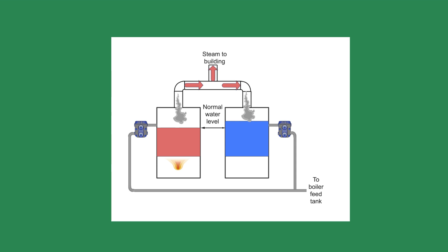They are installed about an inch or two above the normal water line. If the water level reaches this elevation, the traps open and drain water from the boiler to maintain the proper water level. The trap discharge is piped to a condensate or boiler feed tank to reuse the water.